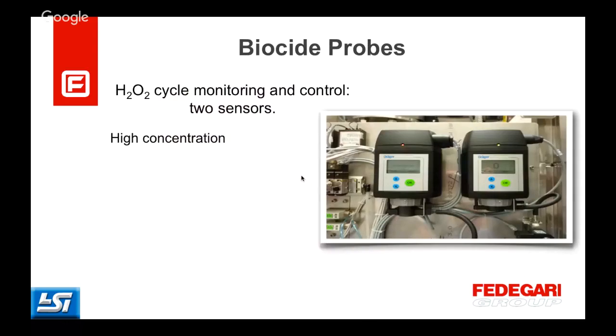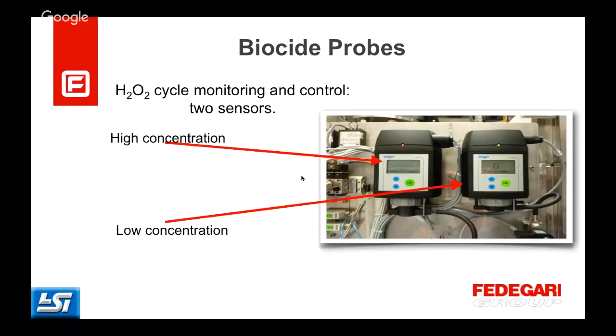So these are the biocide probes. We have one high concentration probe, and this high concentration probe switches to the low concentration probe during the aeration, when the aeration phase has reached a concentration below around 200 ppm. So the last part of the aeration is controlled by the low concentration sensor, from 200 ppm to less than 1 ppm.